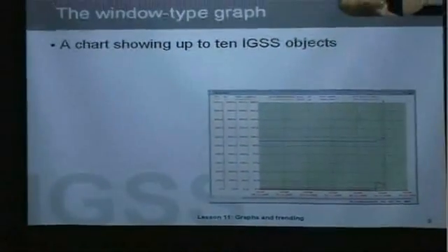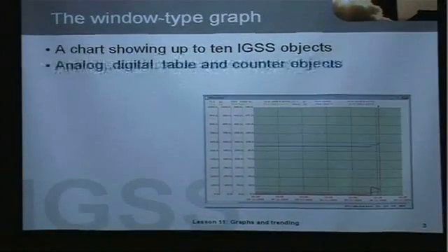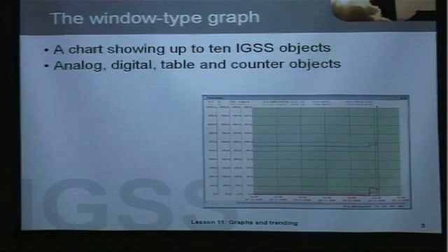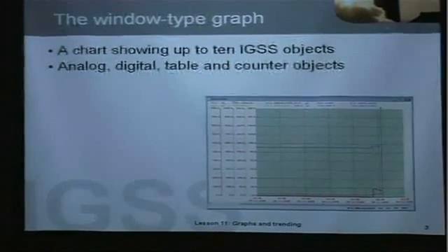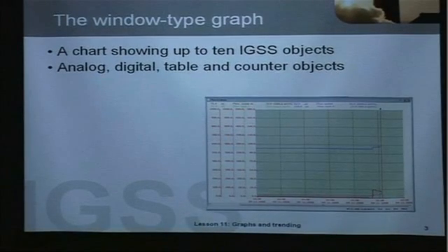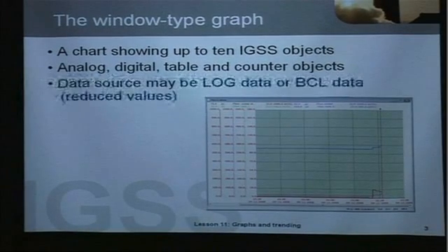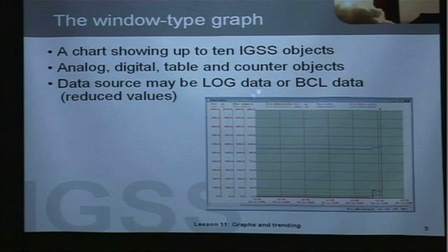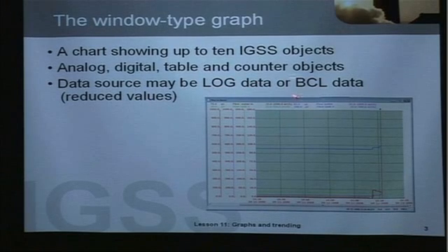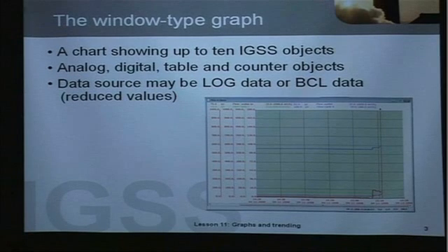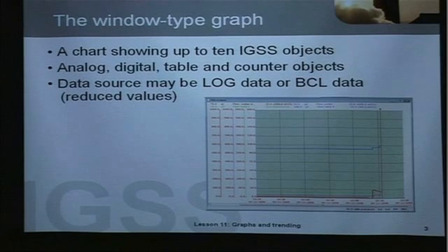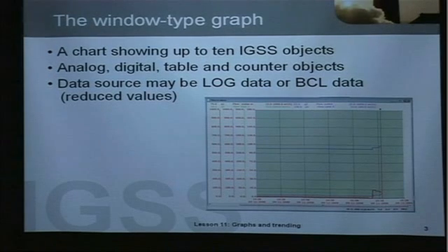In a graph in IGSS you can show up to 10 IGSS objects. You can show analog, digital, table or counter objects. The data source may be log data or BCL data and BCL data in IGSS they are reduced values such as the average minimum and max values for an object during a period.